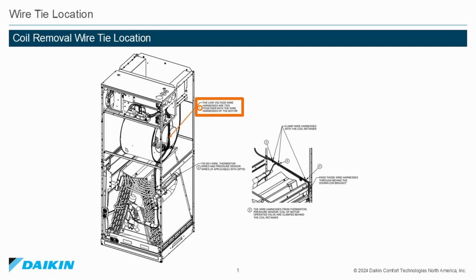Coil removal wire tie location. The low voltage wire harness is tied together with the wire harness of the motor. Tie EEV wires, thermistor wires, and pressure sensor wires, if applicable, with zip ties. Clamp the wire harness with the coil retainer. Pass those wire harnesses through behind the downflow bracket. The wire harness from the thermistor, pressure sensor, and coil of the motor-operated valve are clamped behind the coil retainer.